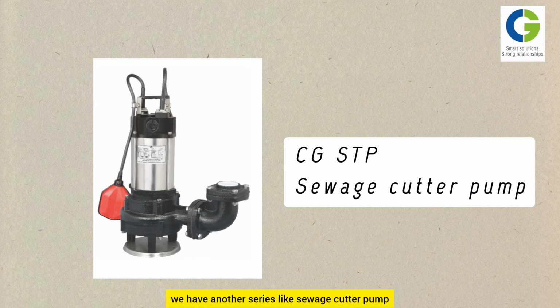Let's see now about the unboxing of our STP pump. Before installation, read this manual clearly. This is the float. The float will be provided only for single phase up to 2 HP. You need to use the SS handle to lift the pump. Anytime you are handling this pump, lift it by using this handle only. Note the serial number. Do not fill any water or any liquid in this place. And the warranty and caution note have to be read before installation.